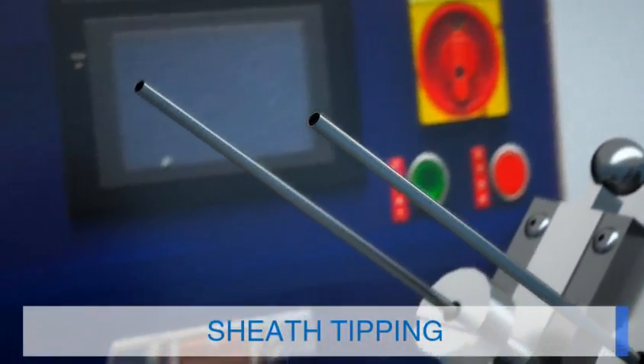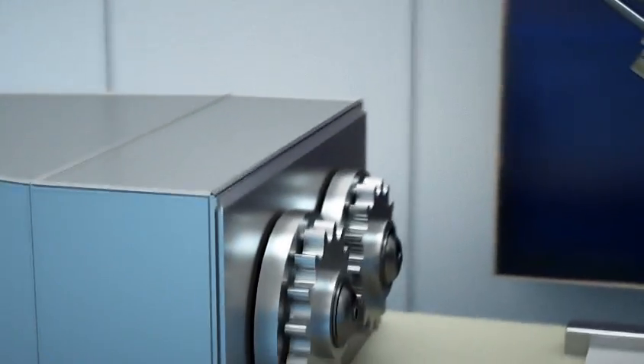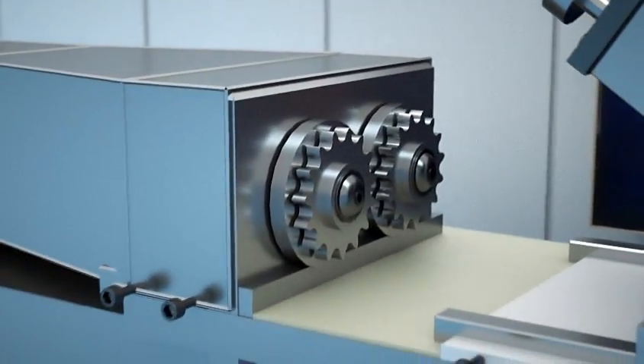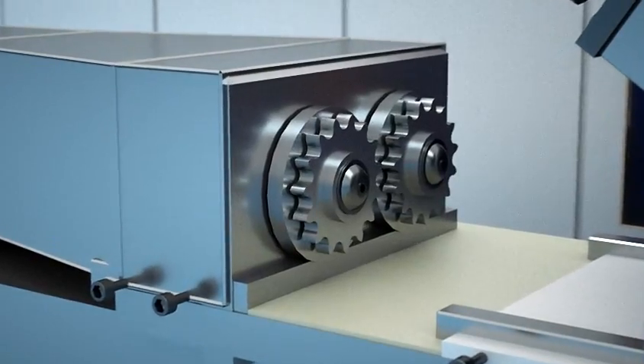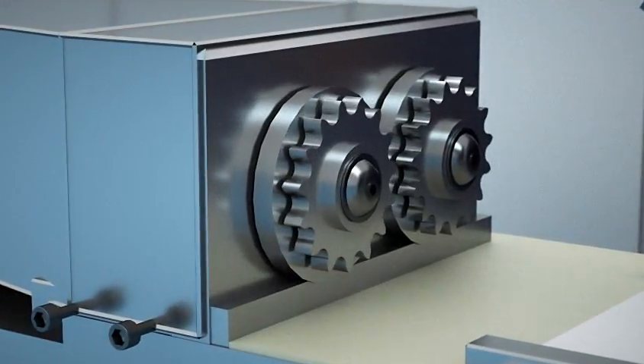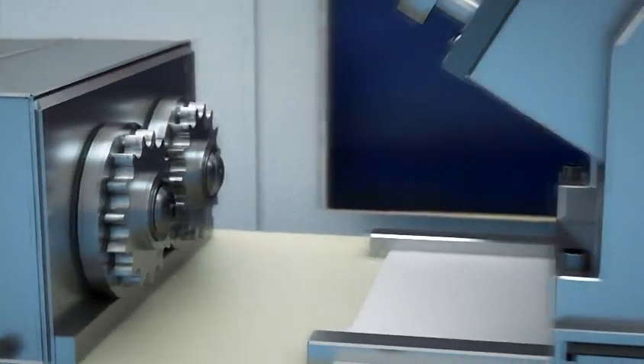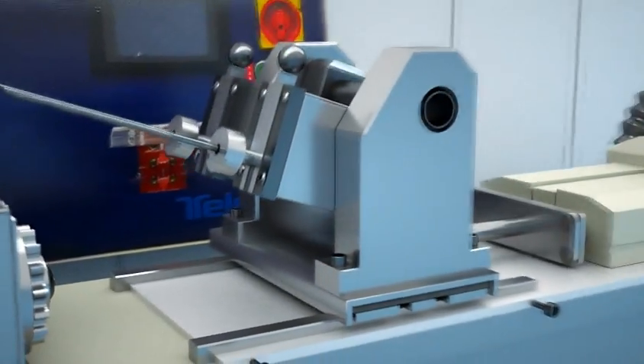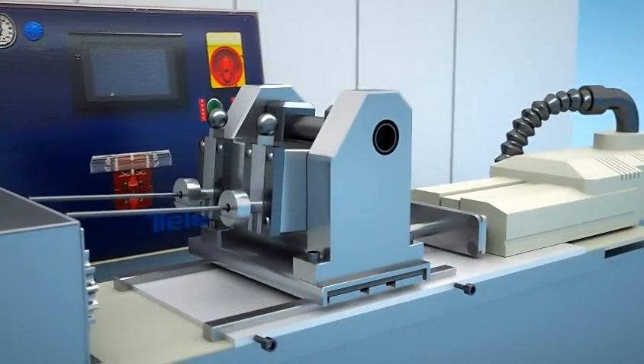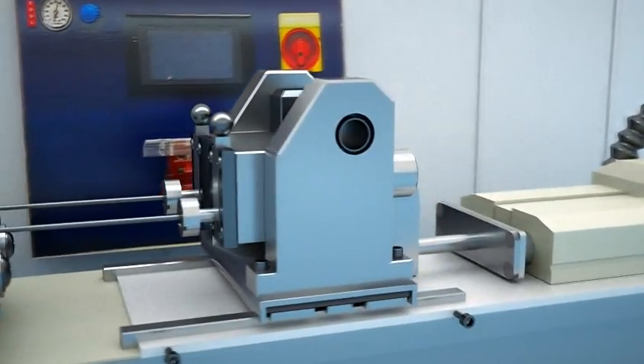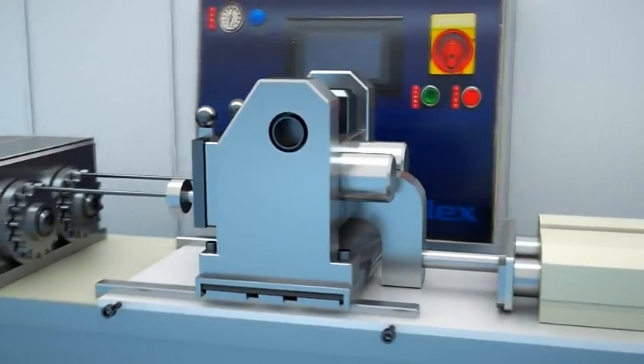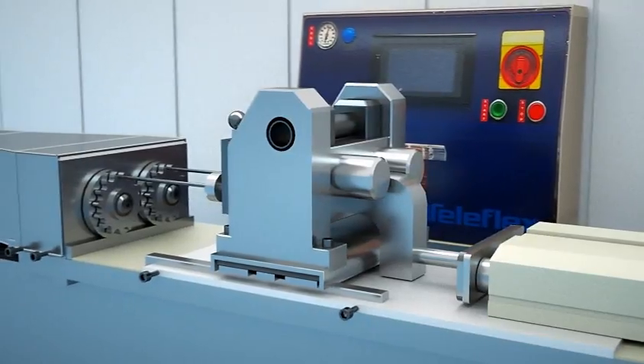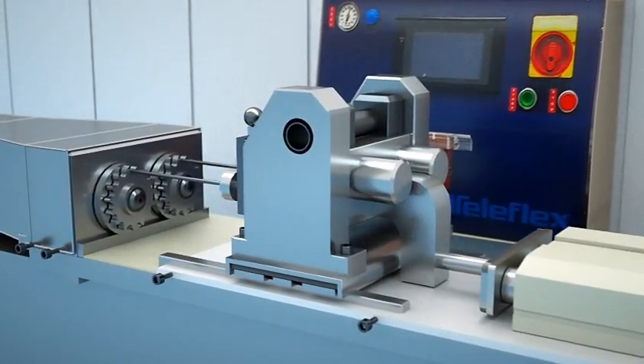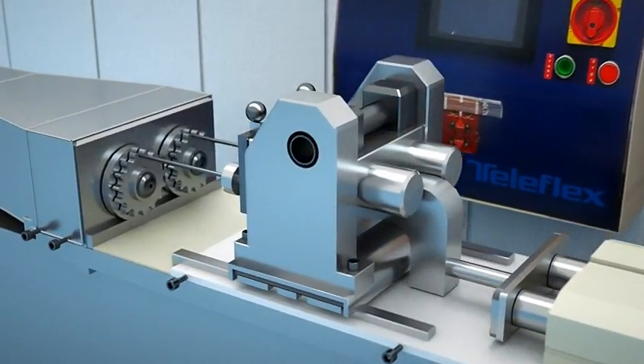Sheath tipping. Sheaths are thermally tipped to achieve two performance characteristics: low insertion force and trackability. Low insertion forces are achieved by optimum tip profile geometry. This is a combination between appropriate taper length to minimize insertion force and adding a radius finish to avoid tip rollback during insertion. The Teleflex Medical OEM team can suggest the most appropriate tip profile for your device.